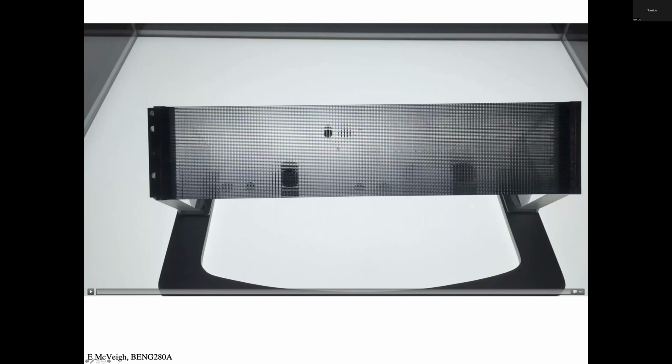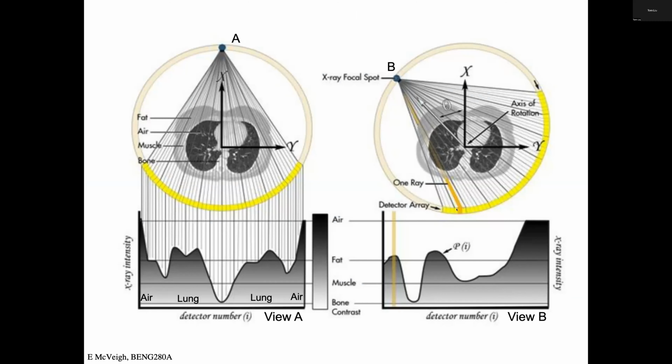The X-rays that hit it get absorbed by this anti-scatter grid. Those X-rays that bounce off the patient and go at a random angle will not give you any useful information about the shadow cast by that patient, so the majority of them get absorbed by this. So what does the signal look like that we measure?